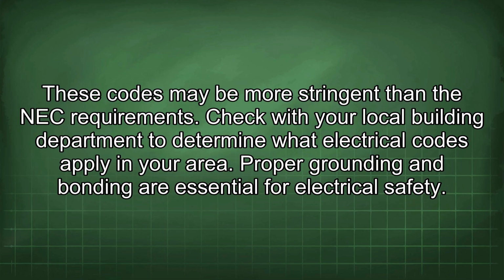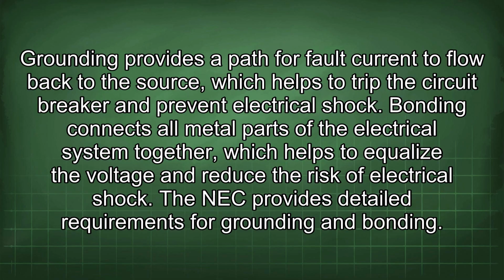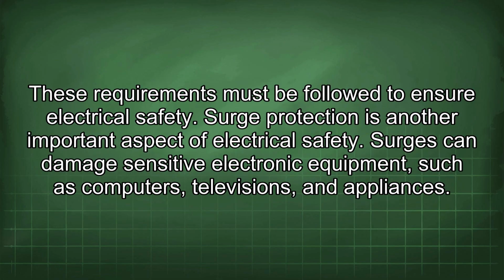Proper grounding and bonding are essential for electrical safety. Grounding provides a path for fault current to flow back to the source, which helps to trip the circuit breaker and prevent electrical shock. Bonding connects all metal parts of the electrical system together, which helps to equalize the voltage and reduce the risk of electrical shock. The NEC provides detailed requirements for grounding and bonding. These requirements must be followed to ensure electrical safety.